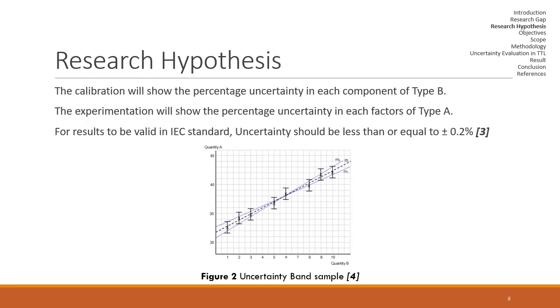During the early stage of this research, we made the research hypothesis that the calibration will show the percentage uncertainty in each component of type B, and the experimentation will show the percentage uncertainty in each factor of type A uncertainty. The Turbine Testing Lab is intended to be constructed in IEC standard. So for any result to be valid in those standards, the uncertainty percentage of TTL should be less than or equal to 0.2%. Finally, a graph showing uncertainty band was expected as shown in figure 2.